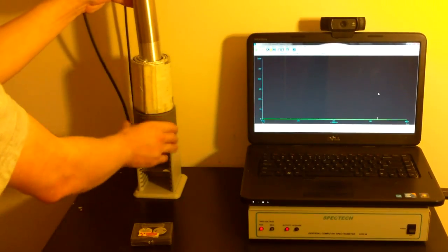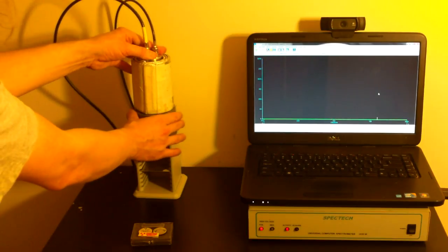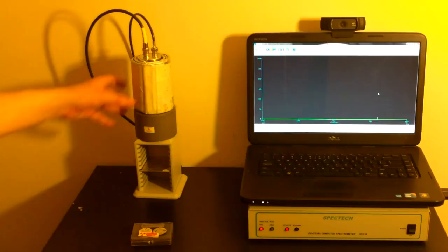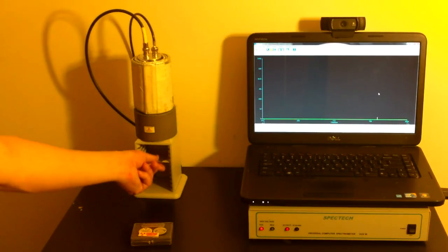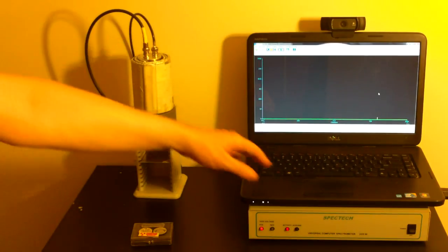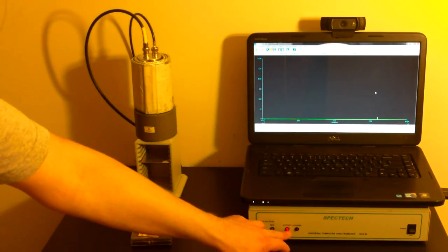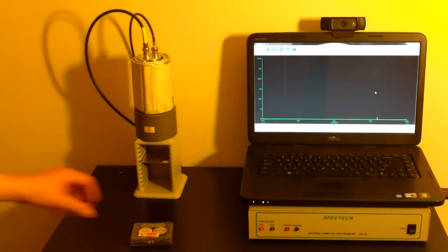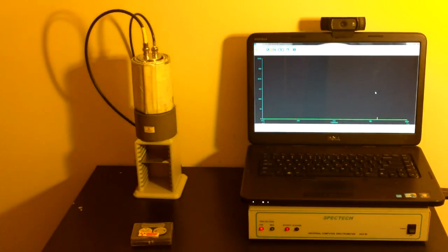And we've stacked it full of lead. This lead unit, this right here, this little donut, comes with the detector itself. And this is some lead I have wrapped around the top of it. So we can put our samples in here in this graduated sample container and see them on the screen right here. Now power is currently on and we're currently detecting activity, although we're not capturing anything right this moment. So let's calibrate this unit and then let's see what we can see.